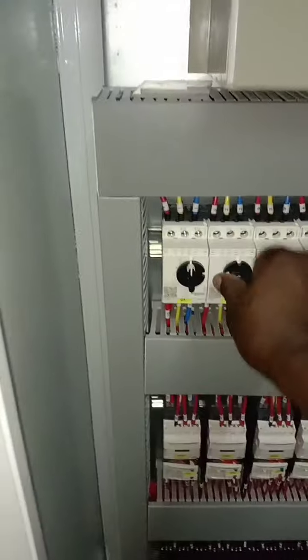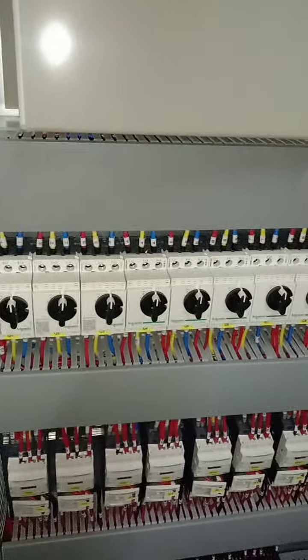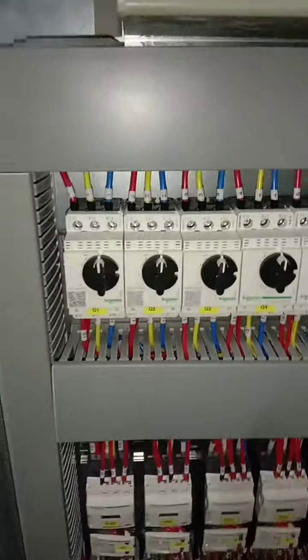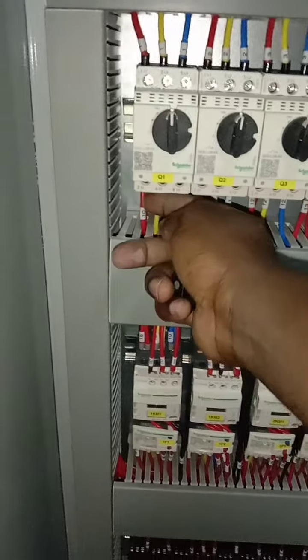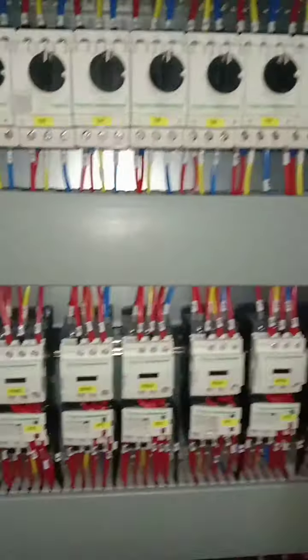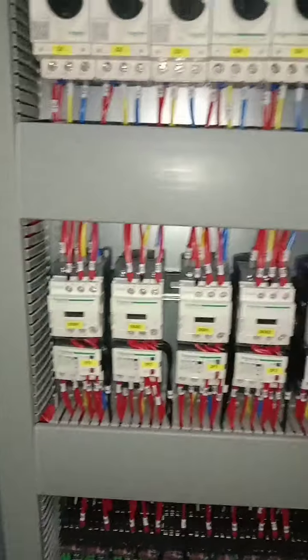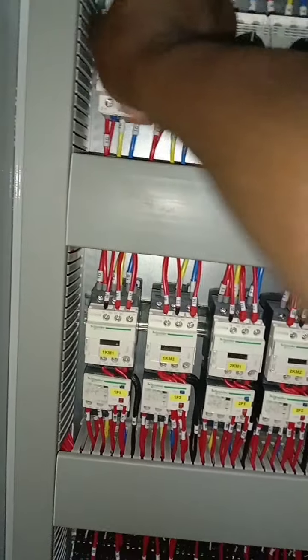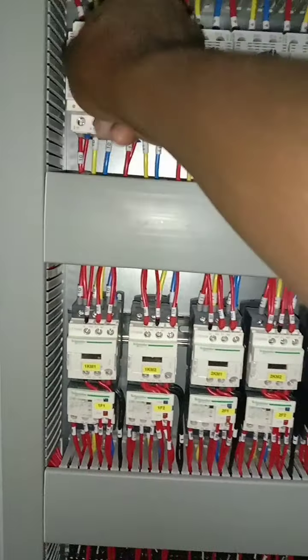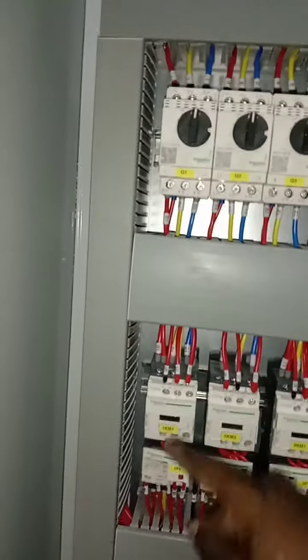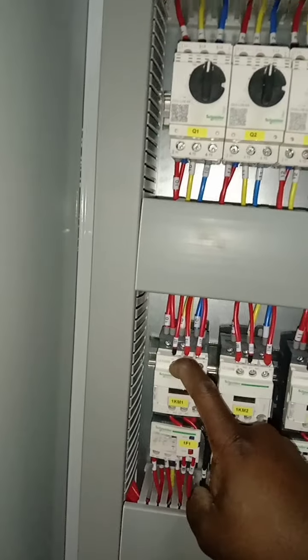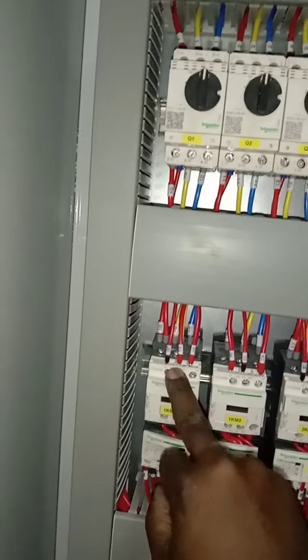Below we have isolator switches, which receive power from downstream of the MCCB, the moulded case circuit breaker. It feeds the isolator switches, and from the isolator switches' output it goes and feeds the different contactors, as you can see below. So once I turn on the isolator switch, it powers the contactor. The contactor will be powered.